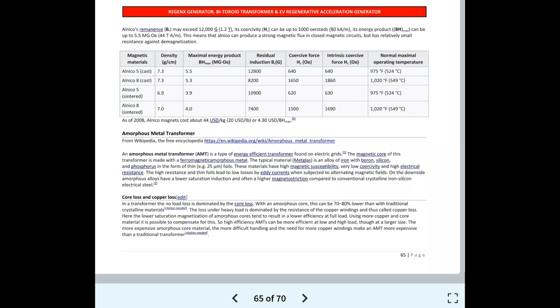The magnetic core of this transformer is made with a ferromagnetic amorphous metal. The typical material, Metglas, is an alloy of iron with boron, silicon, and phosphorus in the form of thin foils. These materials have high magnetic susceptibility, very low coercivity and high electrical resistance. The high resistance and thin foils lead to low losses by eddy currents, when subjected to alternating magnetic fields. On the downside, amorphous alloys have a lower saturation induction, and often a higher magnetostriction, compared to conventional crystalline iron silicon electrical steel.